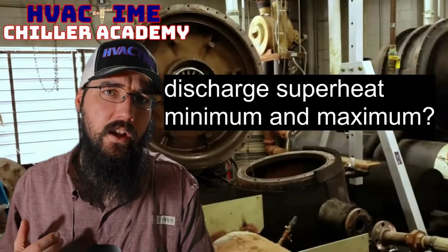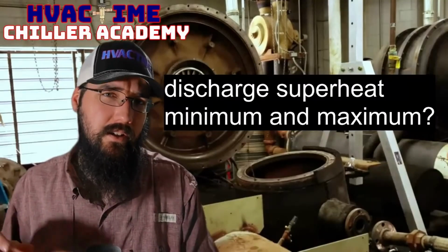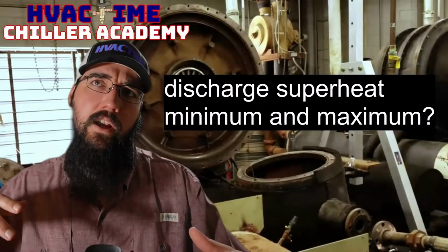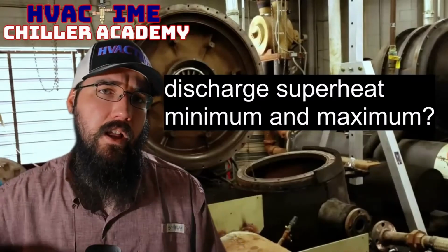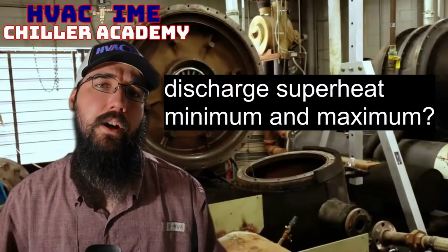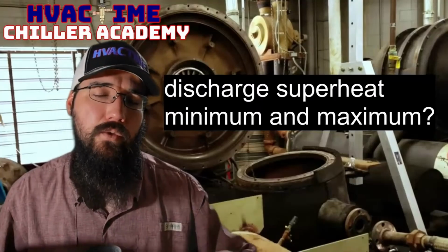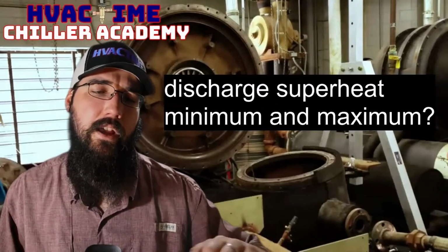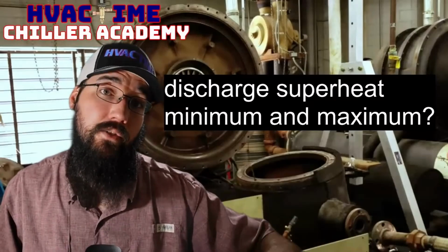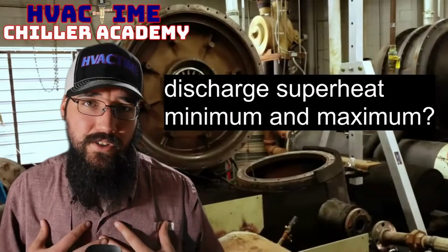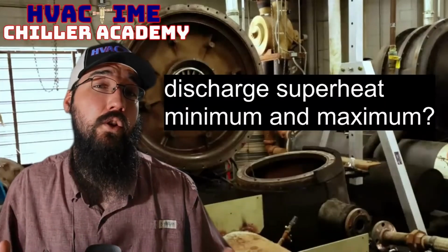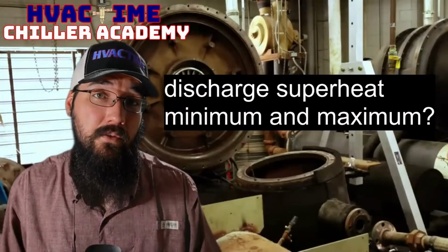So say you've got a lower load, or maybe a little bit of a heavy charge, or you're running your evaporator level a little high compared to where it needs to be, and you've got some lower load conditions, then yeah, you take those factors into account. 10 to 15 on the very, very low end. Personally, I really don't like them to go below 15, even though depending on the compressor, some of them will.